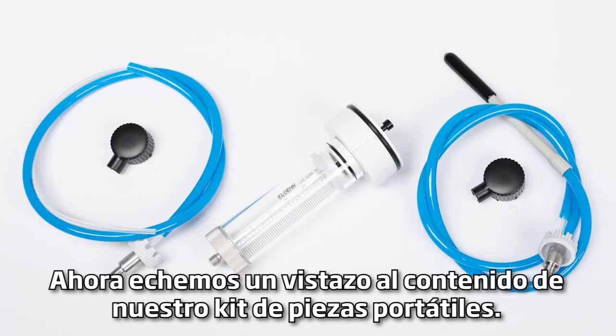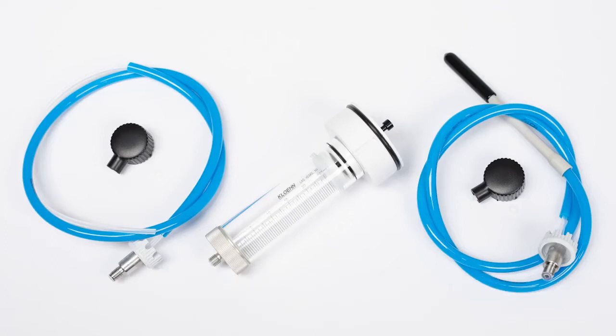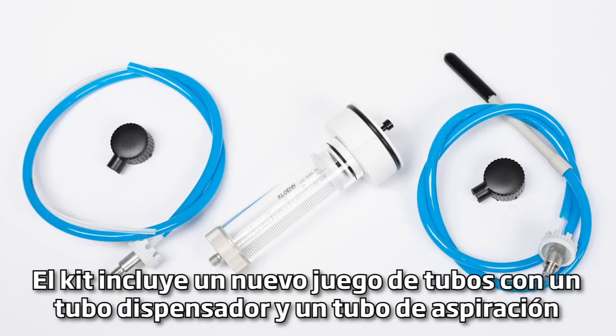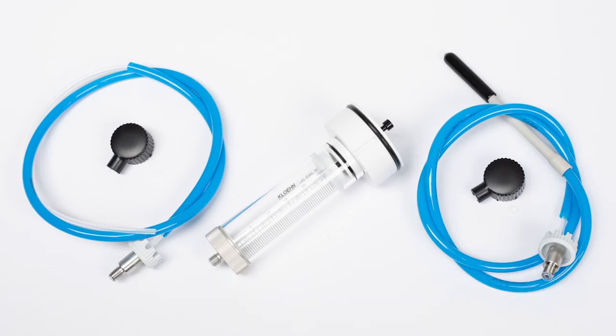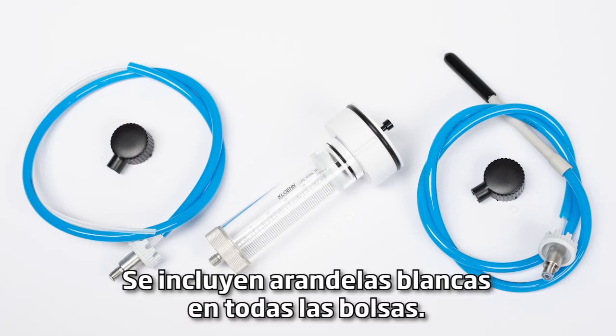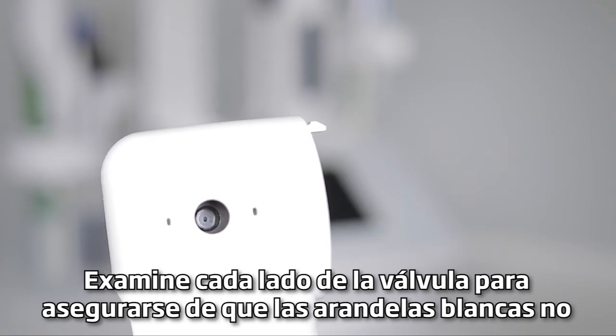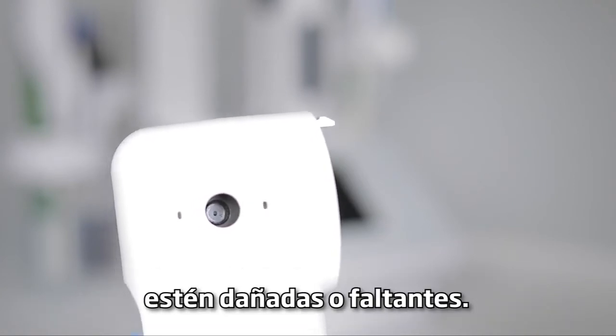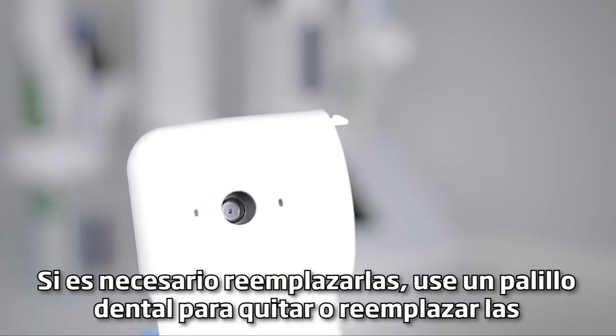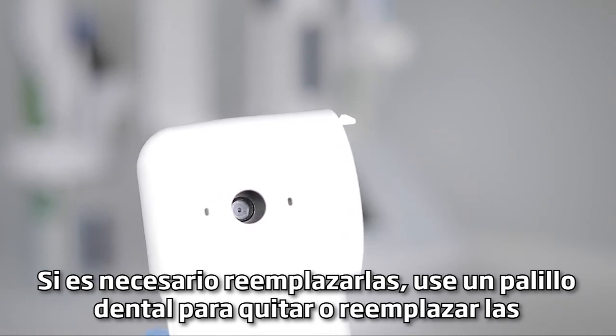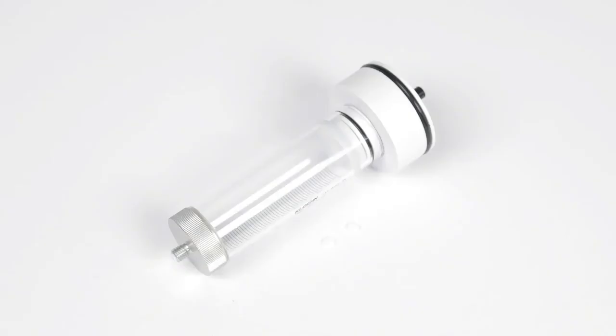Now let's take a look at the contents of our wearable parts kit. Included in the kit is a new set of tubes, with 1 dispensing tube and 1 aspiration tube, and a new syringe. White washers are included in all bags. Examine each side of the valve to ensure that the white washers are not damaged or missing. If they need to be replaced, use a dental pick to remove or replace the washers.